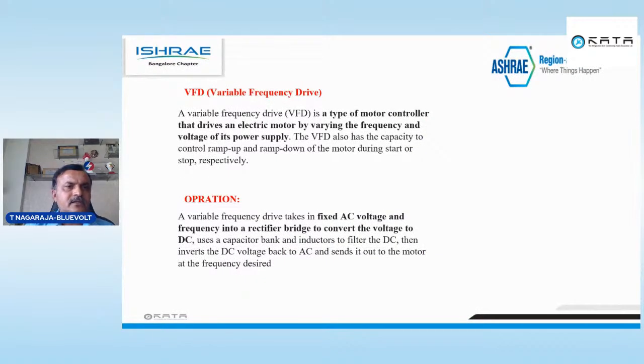Then the other starters are variable frequency drives, that you know very well. A variable frequency drive is a type of motor control that drives an electric motor by varying the frequency and voltage of its power supply. The VFD also has the capacity to control ramp up and ramp down of the motor during start and stop respectively. So whenever you are using a DG, the VFD will help a lot. Suppose 5 motors start at a time, your DG will go down because the load will start up at a time. To avoid this you would have to select a bigger DG. Instead of that, you can go with a soft start, so you can ramp up and ramp down slowly.